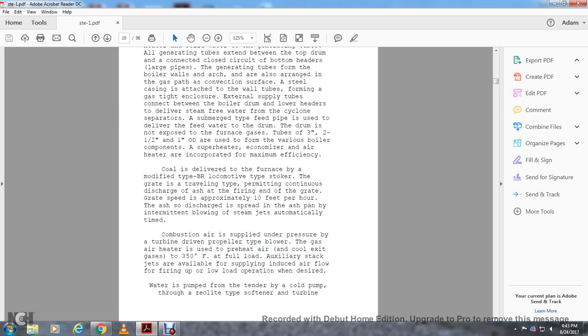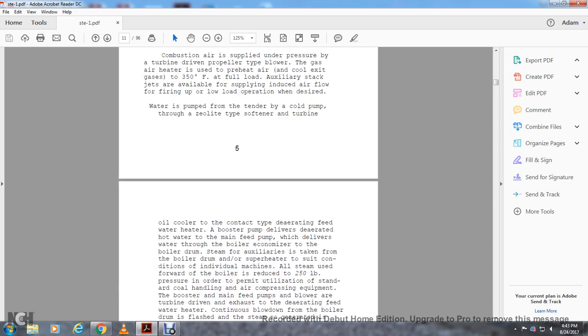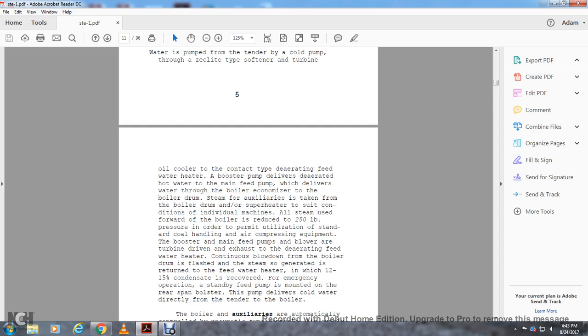The gas air heater is used to preheat the air, and cool exit gases to 350 degrees Fahrenheit at full load. All auxiliary stack jets are available for supplying induced airflow with the firing up, the low load operating when desired. Water is pumped from the tender by the cold pump through the zeolite type softener and turbine oil cooler in contact with the de-aerating feed water heater. The booster pump delivers the de-aerated hot water to the main feed pump, which delivers the water through the boiler economizer to the boiler drum.